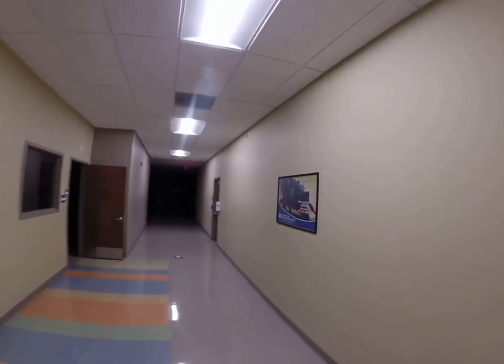So oftentimes you'll see these key switches, sometimes mounted in the ceiling pads and sometimes mounted on the wall where nobody could reach them. This is actually a test switch for a rooftop unit. And if you can't really see it, it says RTU number 5 on it. Basically, if I turn that switch to the right, it'll turn off the rooftop unit, which is part of the fire alarm system. We call this fan shutdown. And fire marshals come in and they want to test that your fan shutdown works. And what they'll do is they'll test it by using the key switch.